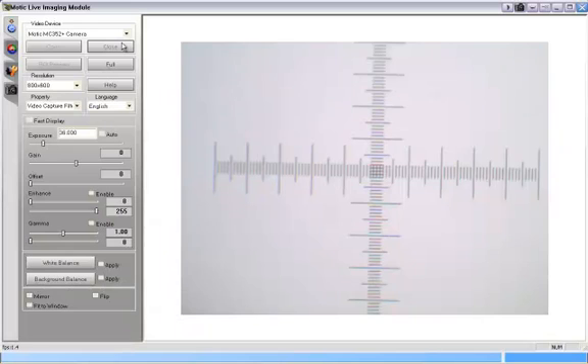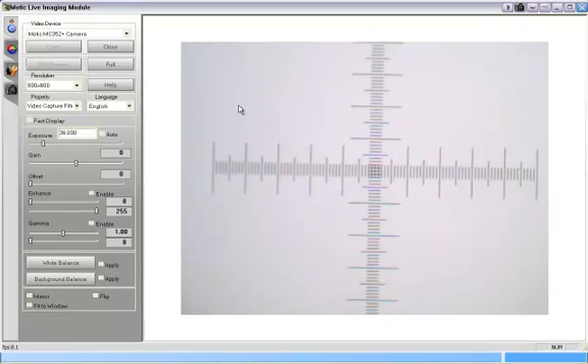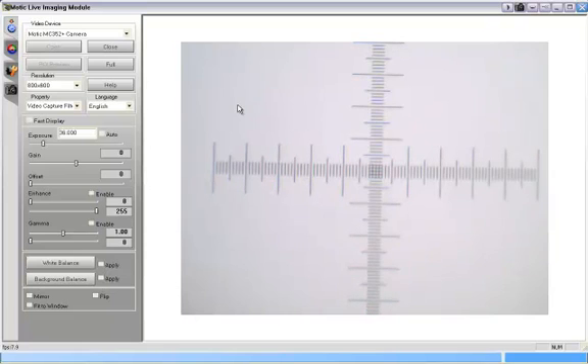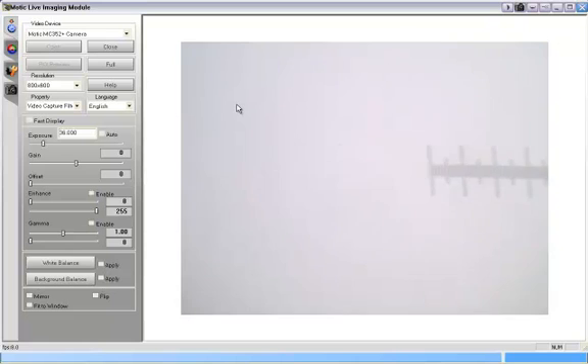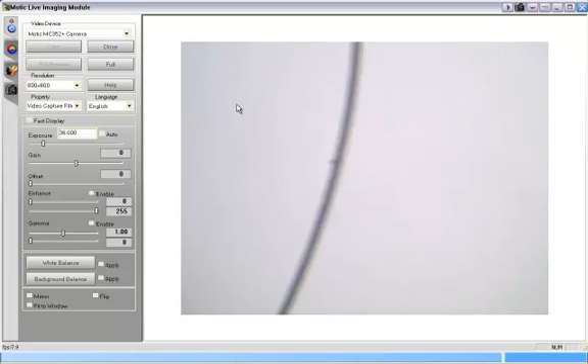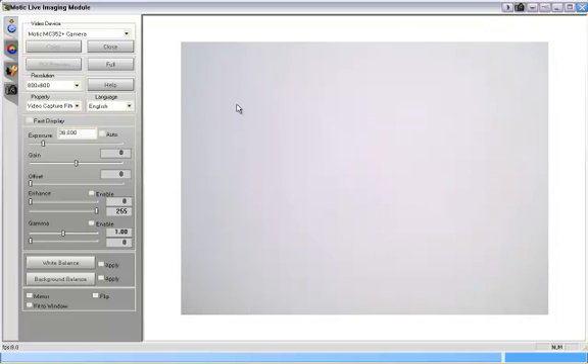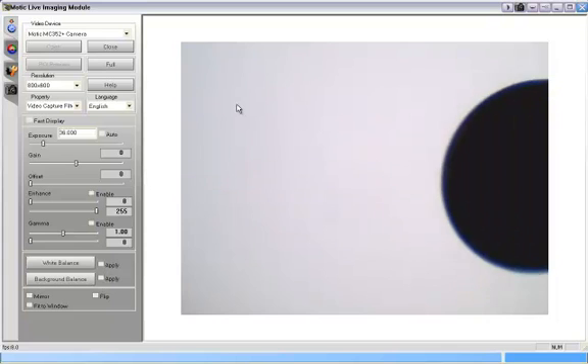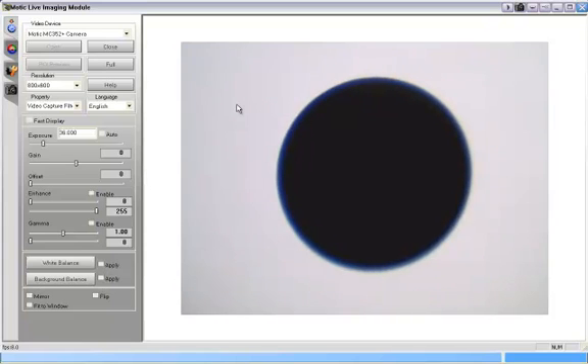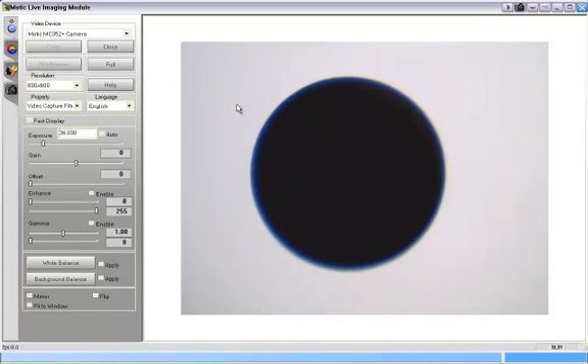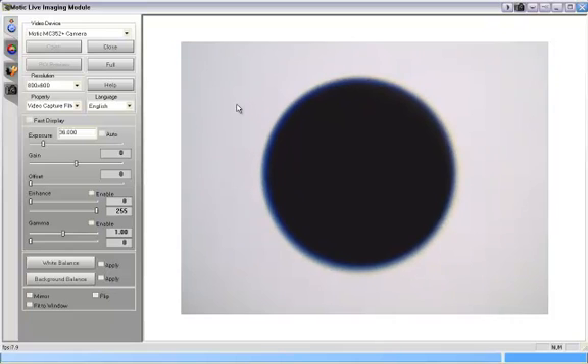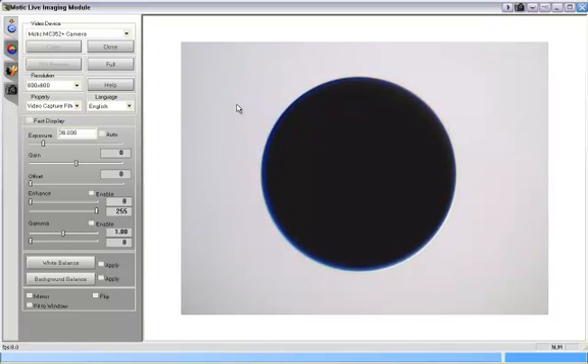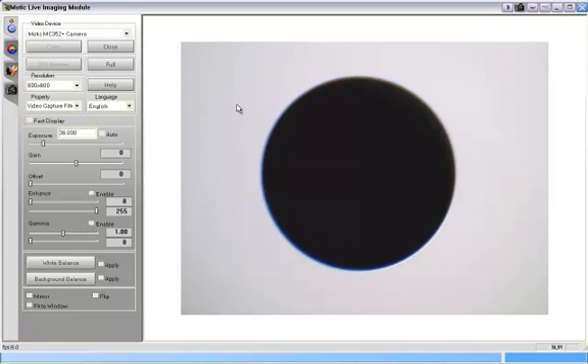I've already placed the calibration slide underneath the microscope and using the 10x objective focused on the crosshairs. So use the focusing controls to focus and now use the mechanical stage or your thumbs to slide the slide to the proper position where you can see a calibration circle that is big enough but not too big so you can see the entire circle.